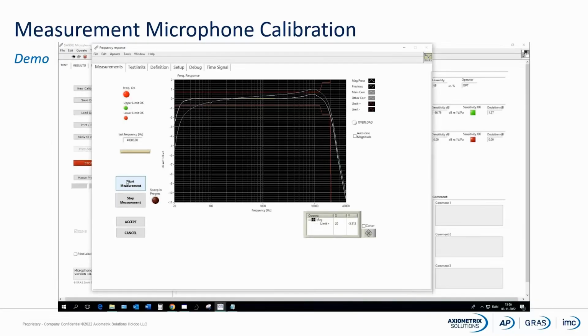But I can see we still have some issues at the low frequency, and we also have a little issue at the higher frequency. The issue at the low frequency is actually due to I have forgotten that we have a 20 hertz high pass filter in our power module. So I have now switched this off, and we can see that we are measuring very, very flat from 20 hertz and up. We still have a little issue in the top.